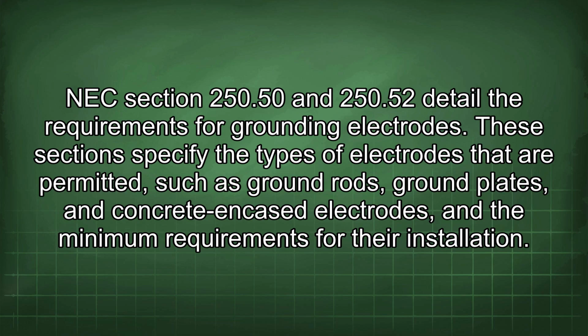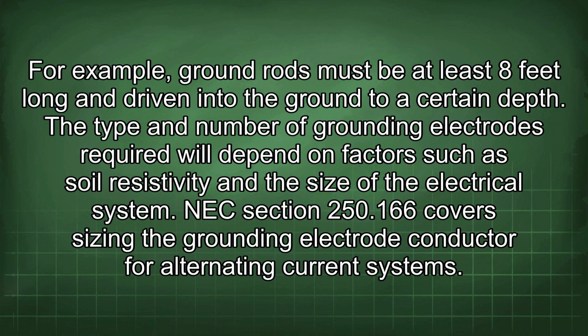NEC Sections 250.50 and 250.52 detail the requirements for grounding electrodes. These sections specify the types of electrodes that are permitted, such as ground rods, ground plates, and concrete-encased electrodes, and the minimum requirements for their installation. For example, ground rods must be at least 8 feet long and driven into the ground to a certain depth. The type and number of grounding electrodes required will depend on factors such as soil resistivity and the size of the electrical system.